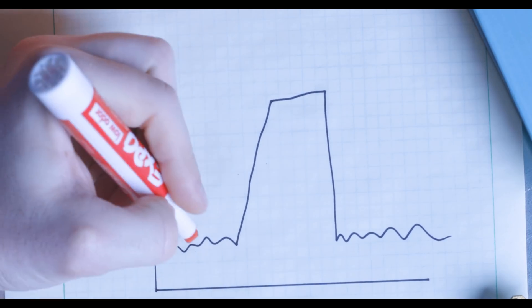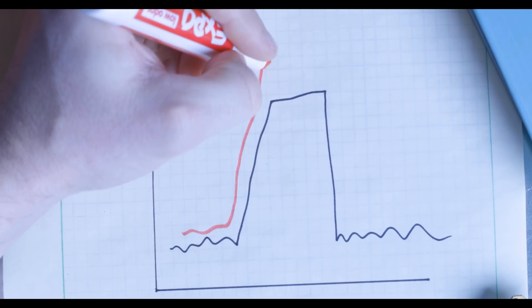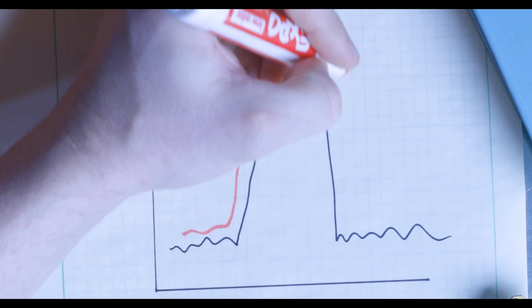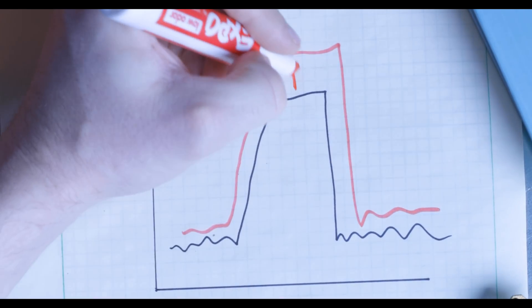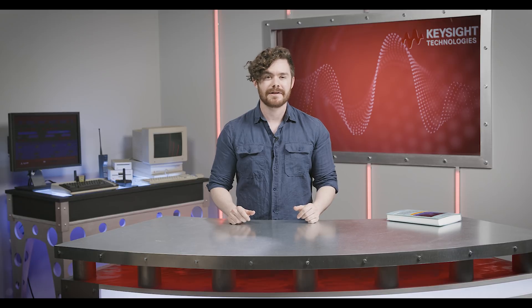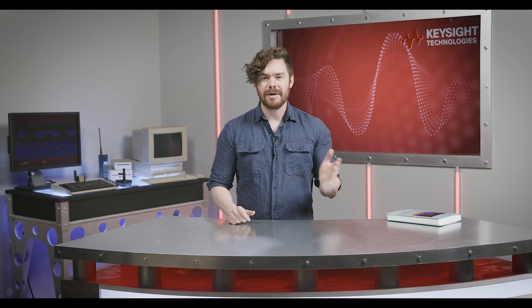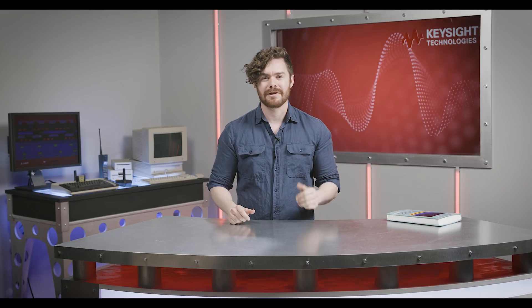Number one, you can increase the power of your signal. This will boost your signal away from the noise. This is a great method because you don't lose any measurement speed, but you have to be careful to stay within the power limits of your equipment.